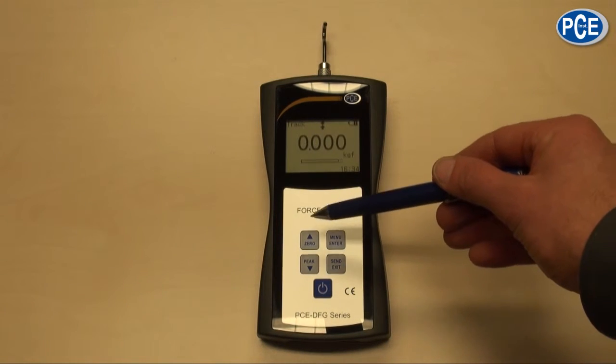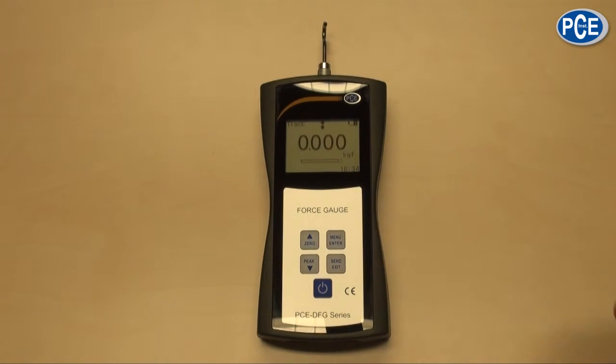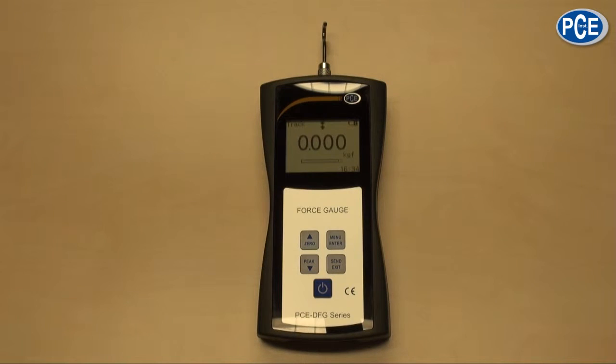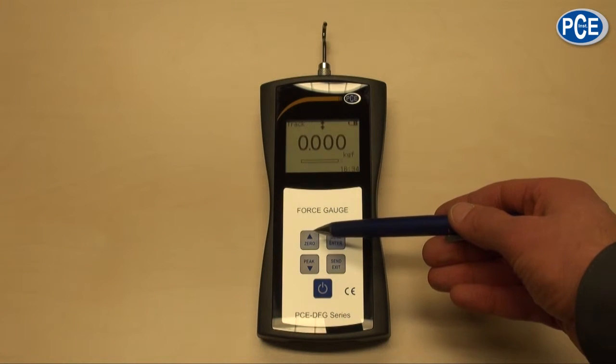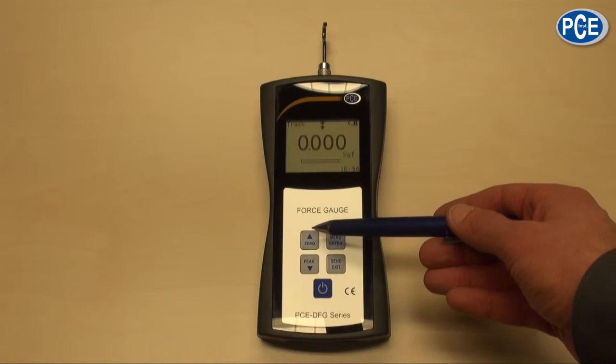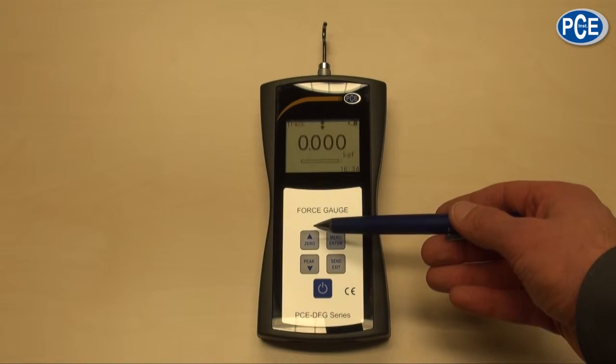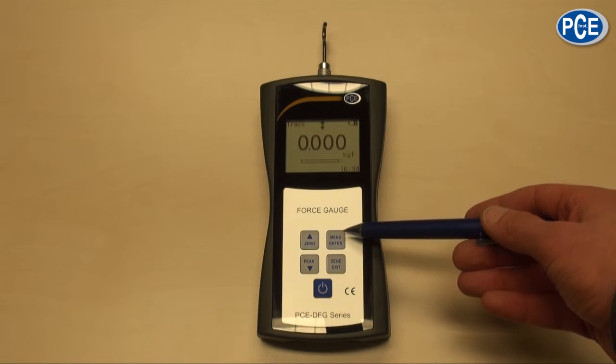The white buttons all have a double function: one function for measuring and one function for the menu. The zero button or the arrow up button has in the menu the function arrow up, and during the measurement the zero function, so you can note the measurement.